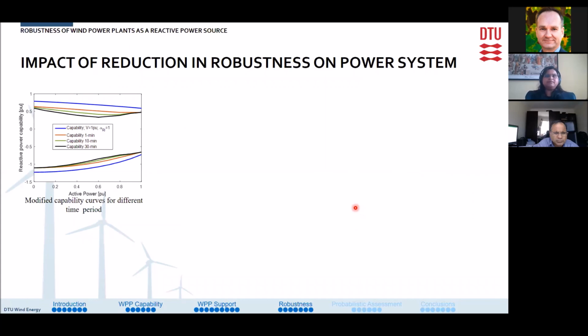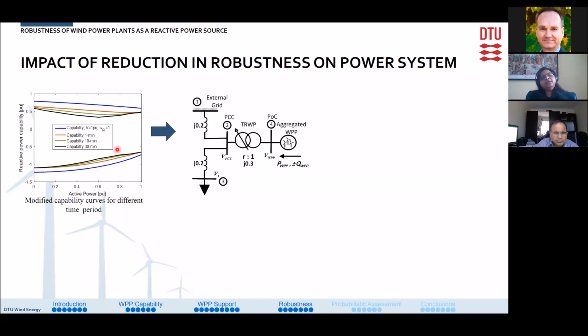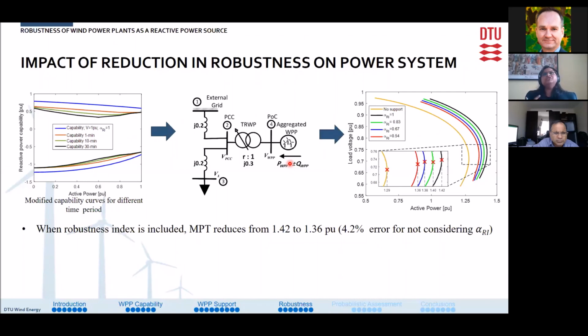Now, we got the robustness index in the previous slide, and with that robustness index, we modified the capability curve for the three different time periods. And we can see here, as expected, the capability curve for the 30-minute time period is the most restricted one. And then what we did is we included this restricted or modified reactive power capability into the four-bus power system as described earlier, and we studied the impact of reduction in robustness on the power system. So the black curve here represents the robustness index of 1. That means none of the uncertainties are included here. So we see that with this, we get a maximum power transfer of 1.42 pu here.